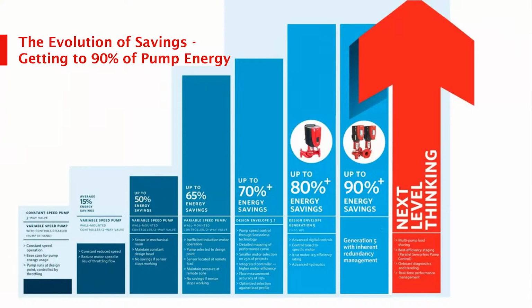You get insight from flow, which embedded technology now provides, letting you make improved future decisions. You get flow in the secondary system, flow on the condenser side, and even if you have a flow meter on the primary loop, you can validate whether it makes sense. Increasingly, as you move to more modular technology, making a pump decision now doesn't hamstring what you want to do with the chiller or boiler two years from now.